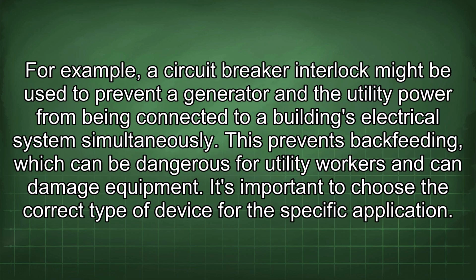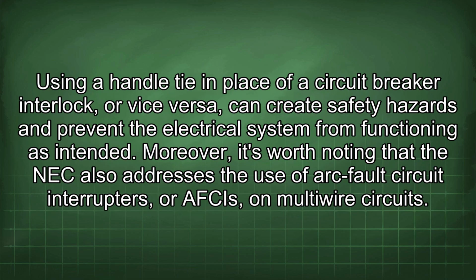For example, a circuit breaker interlock might be used to prevent a generator and the utility power from being connected to a building's electrical system simultaneously. This prevents backfeeding, which can be dangerous for utility workers and can damage equipment. It's important to choose the correct type of device for the specific application. Using a handle tie in place of a circuit breaker interlock, or vice versa, can create safety hazards and prevent the electrical system from functioning as intended.